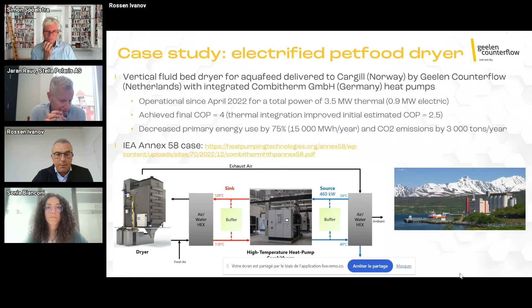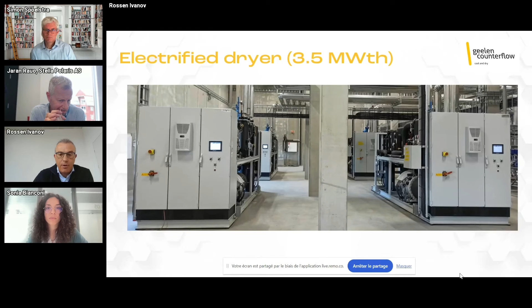The trick there with the improvement of the COP is to use different temperature levels within the dryer in order to minimize the lift at every stage. The case is described in detail in the International Energy Agency Annex 58 Heat Pump Technology Center. This is the plant room with the dryers, for a total of 3.5 megawatts thermal, 4 heat pumps, and 10 compressors overall. I'll skip the video for the sake of time. It's on YouTube, and you can have a look at it. It is showing the factory and the dryer with implementation.